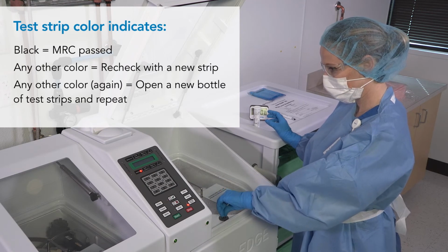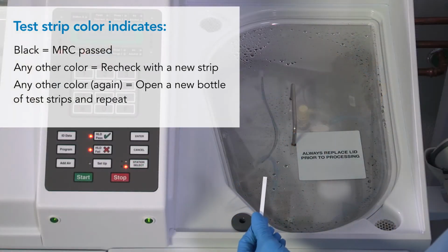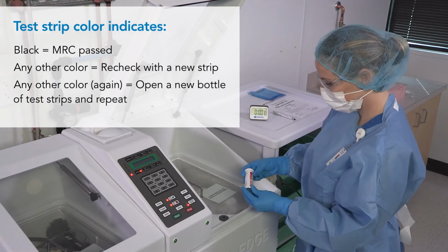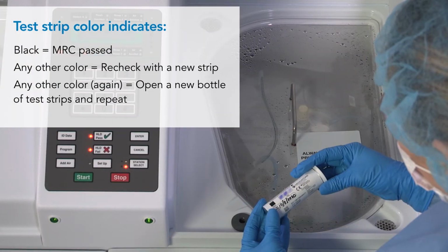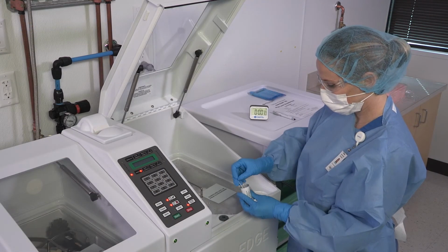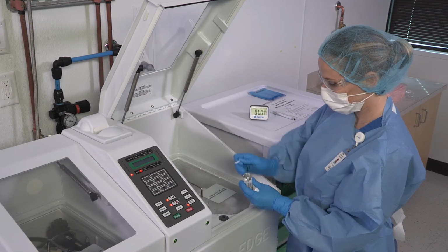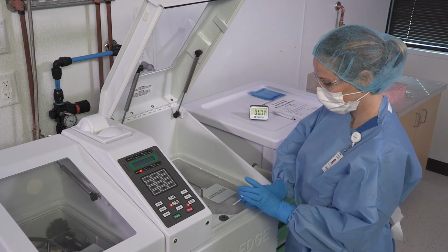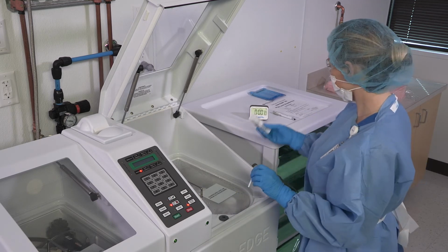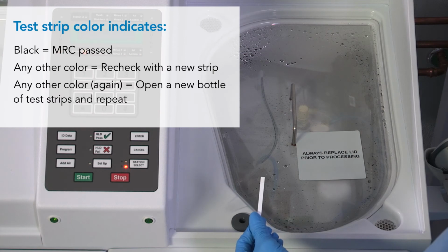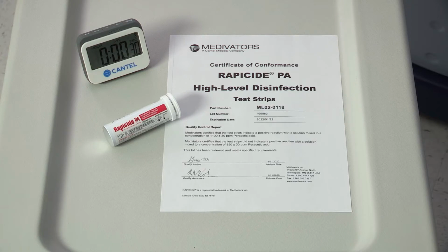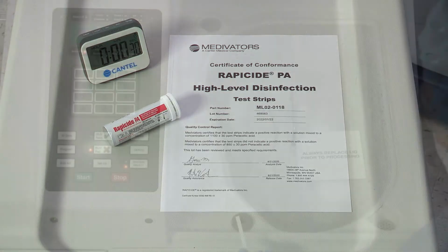If the test strip color indicates the disinfectant MRC was not met during the cycle, check the expiration date on the test strip bottle and confirm the test strips have been stored properly. If not expired, use another test strip from the bottle and retest while ensuring you are following the test strip IFU. If the MRC fails again, open a new bottle of test strips and repeat the test. Test strips are sensitive to light and moisture. Be sure to replace the test strip bottle cap after each use.